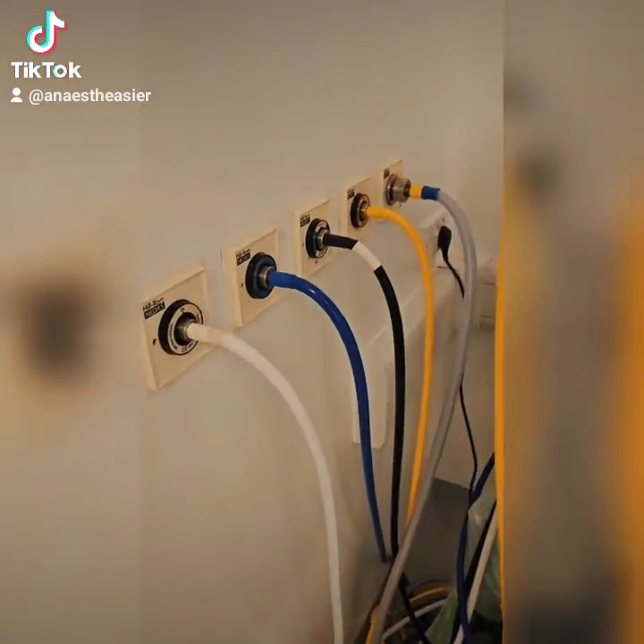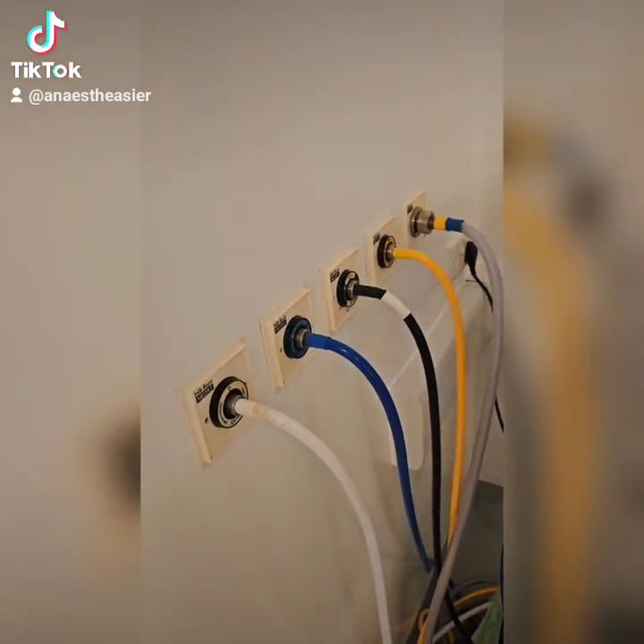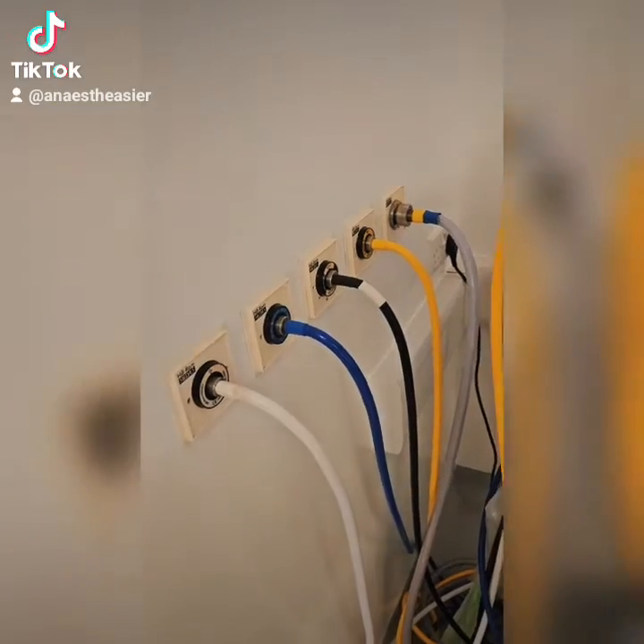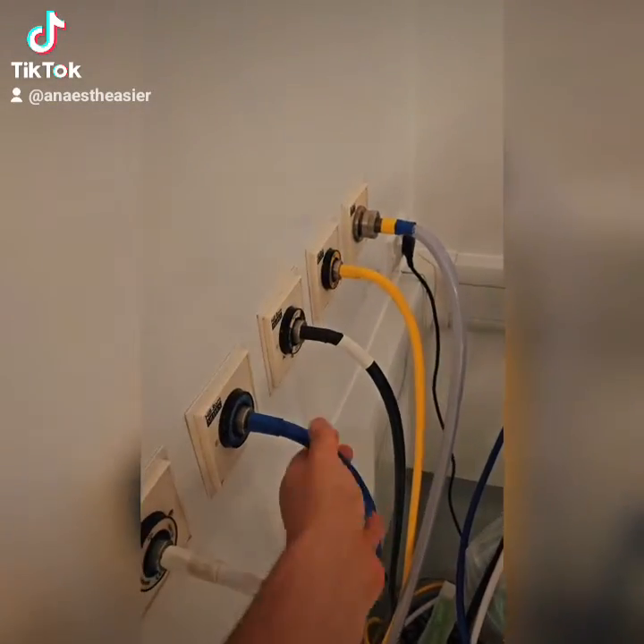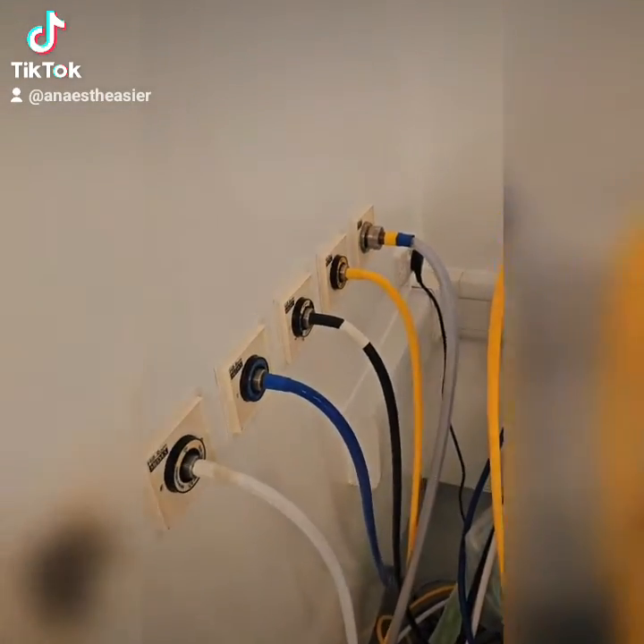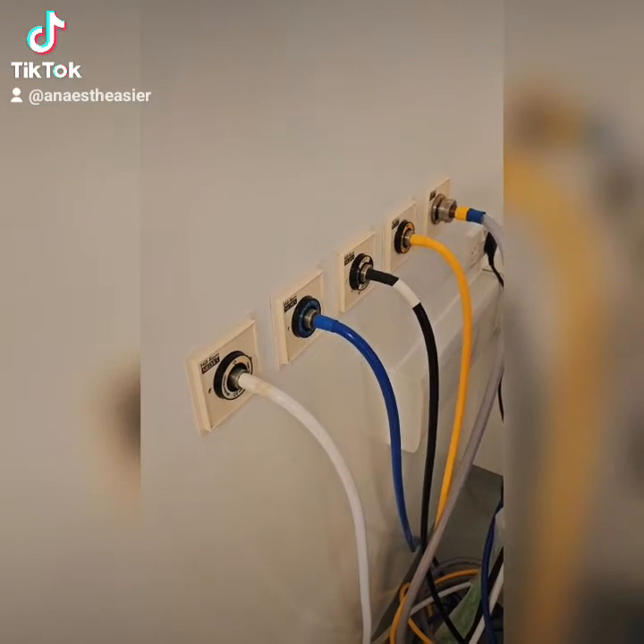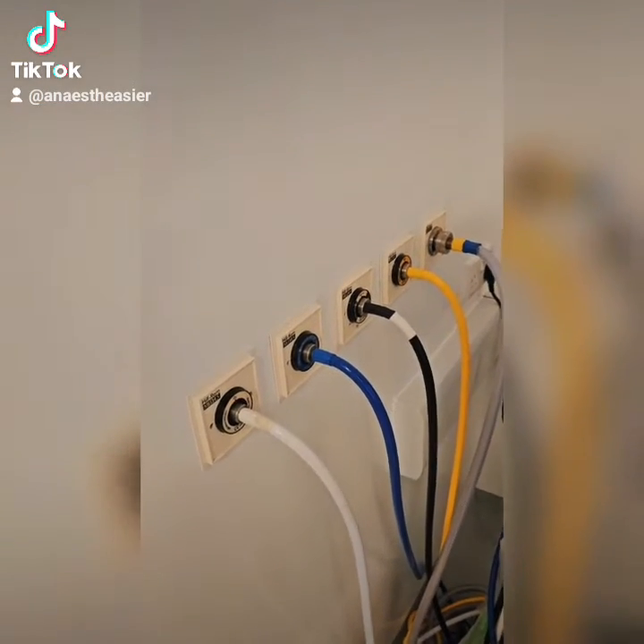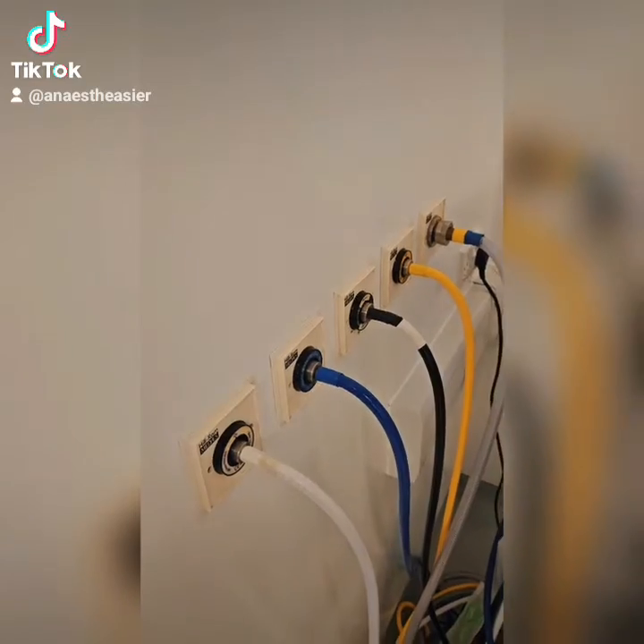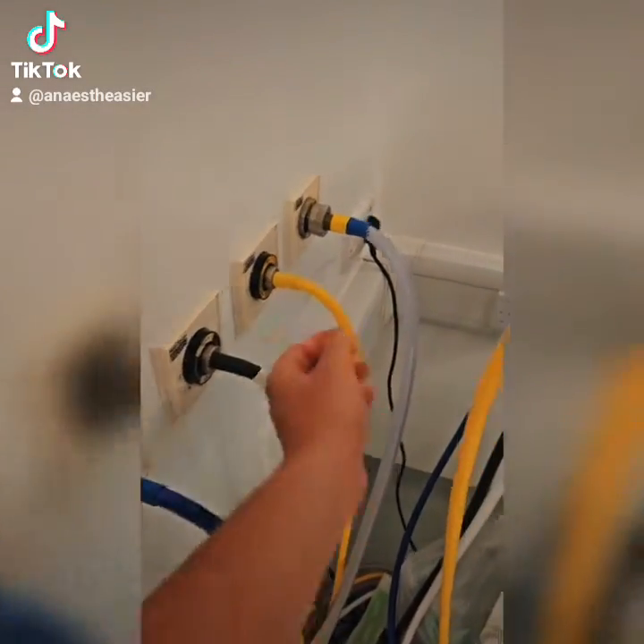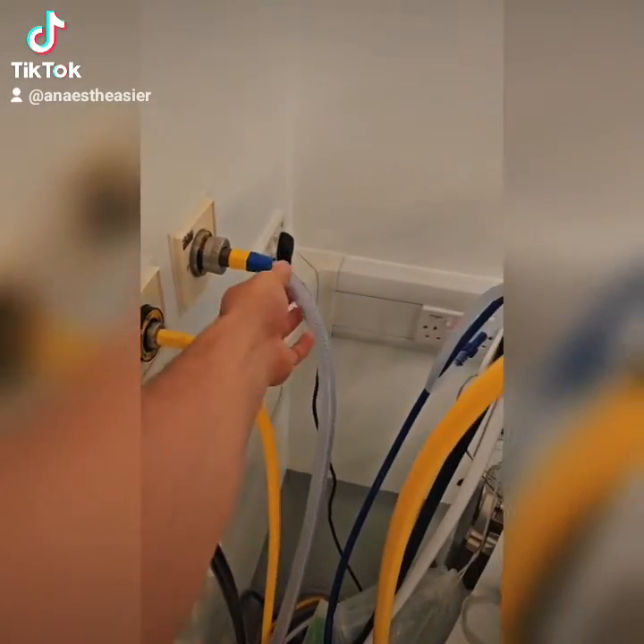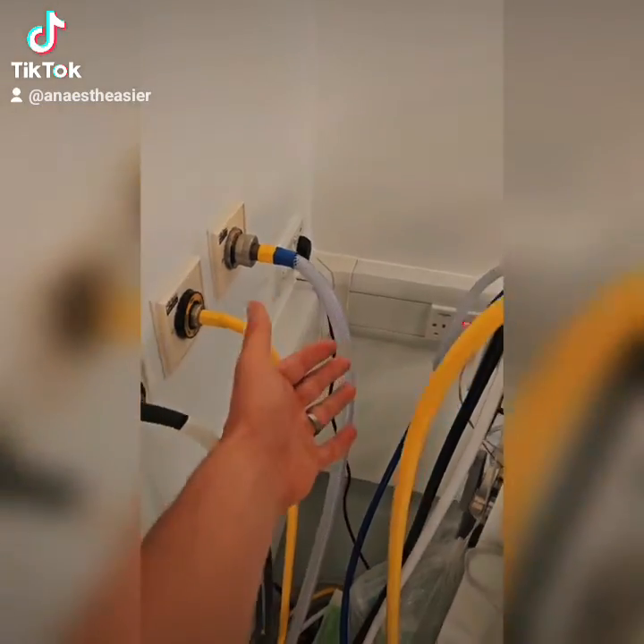This is the gas supply. So the anaesthetic machine is plugged into a whole bunch of gases from the wall supply. So white is oxygen, blue is nitrous, so nitrous oxide, which is a bit of sedation, a bit of pain relief. It's bad for the environment, it works well. There's a whole argument as to whether you should give it or not. Black is just air, yellow is suction, and this clear one is anaesthetic gas scavenging.